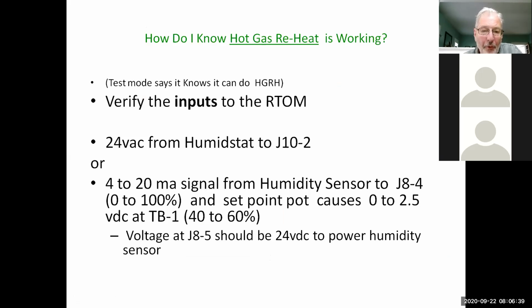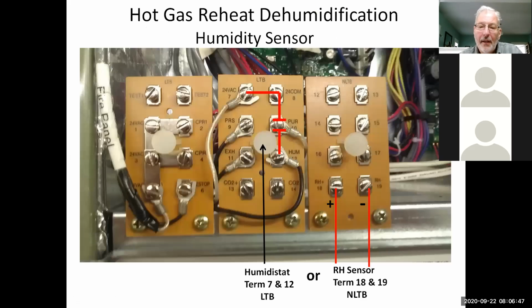You can use it two different ways. You can use a 24-volt humidistat or a 4 to 20 milliamp control, Trane American Standard control. How do you know you have a dehumidification rooftop? You're probably going to have a lot of extra boards in here. So if you're using a Honeywell or just a set of normally open contacts, you'd go between pins 7 and 12. If you're using a milliamp control, you go between pin 18 and 19. So if you have these extra boards in here, that usually tells you that you have a dehumidification unit.